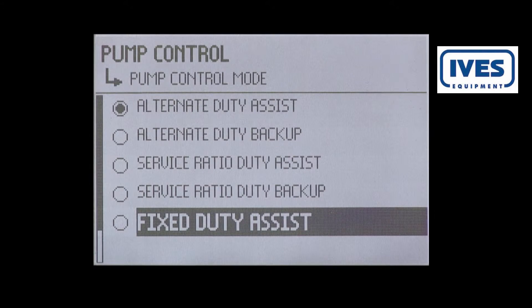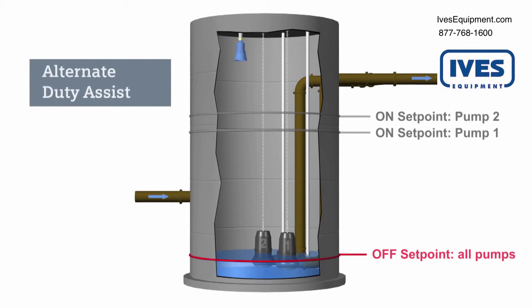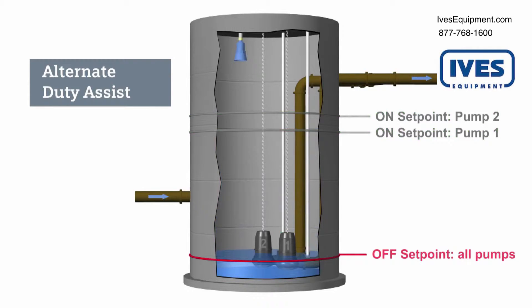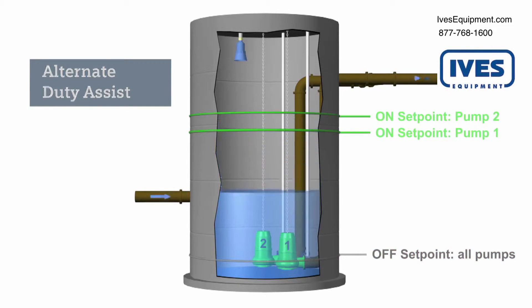The alternate duty assist routine rotates between both pumps to control the liquid level. Pump one will start first. If it cannot keep up with the inflow, then pump two will turn on and assist pump one. Both pumps will run until the liquid level reaches the pump off setpoint. On the next cycle, pump two will be the first pump to start. Pump one will assist pump two if it is necessary. The starting pump will continue to alternate between pump one and pump two after each filling cycle.